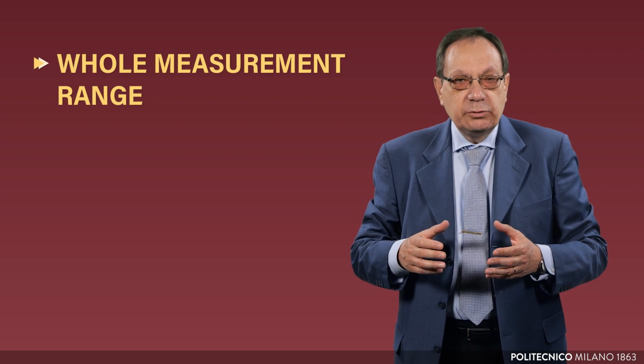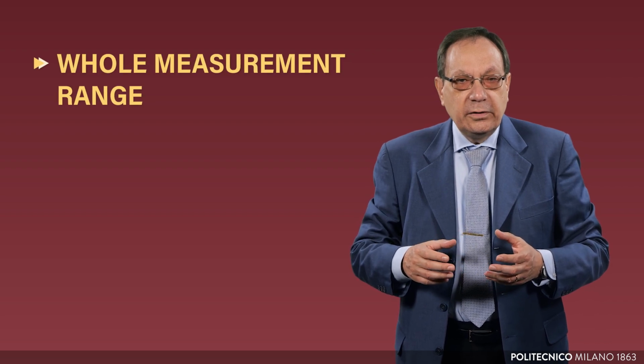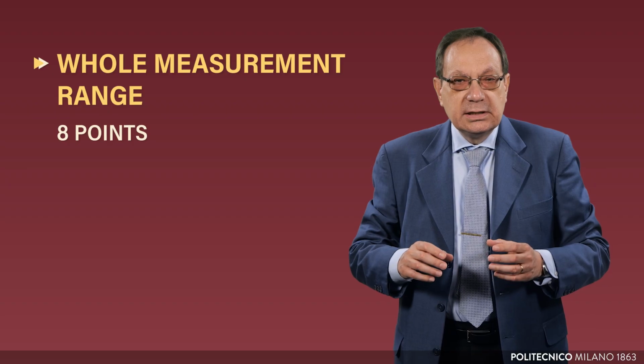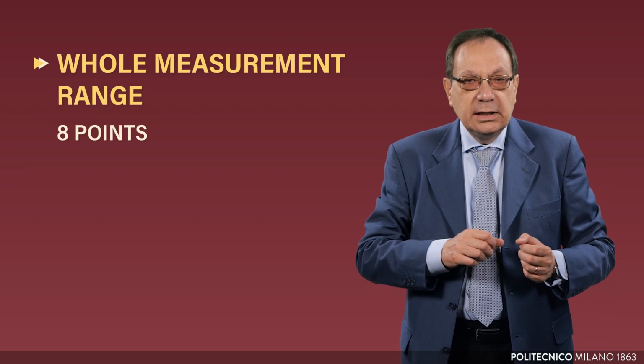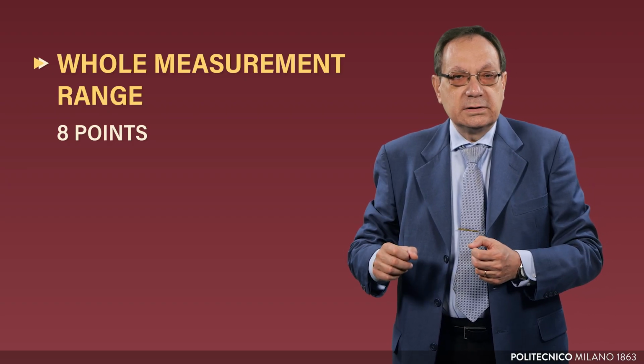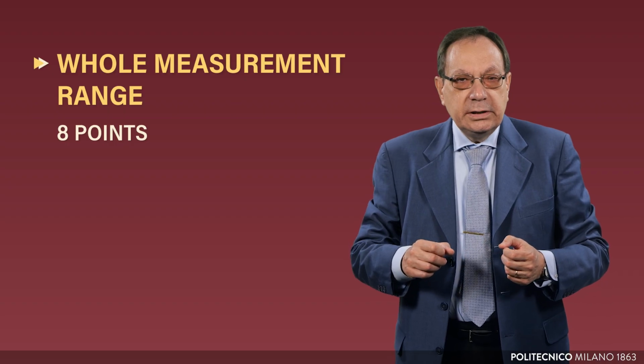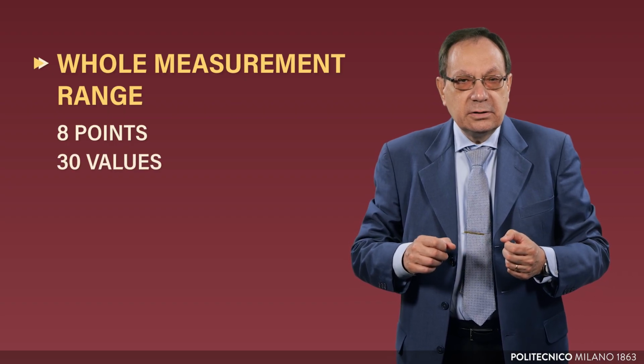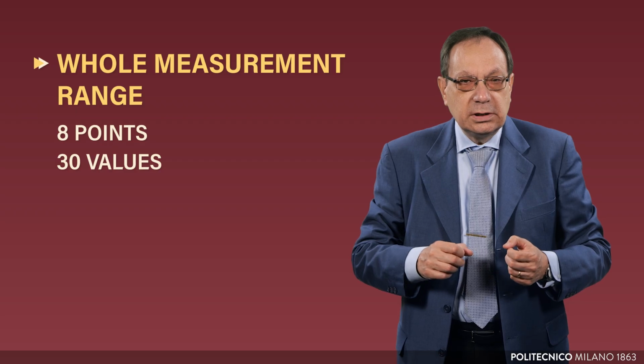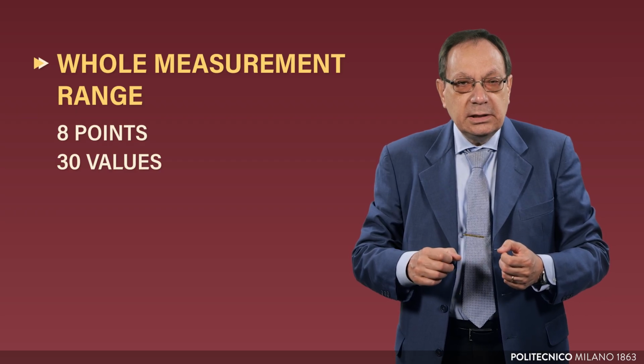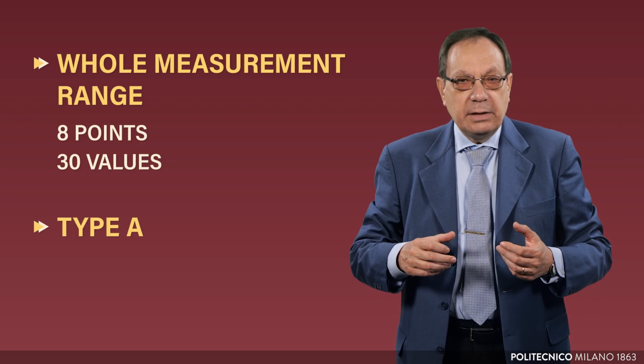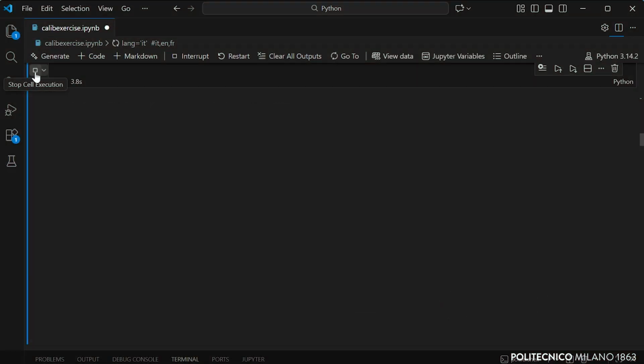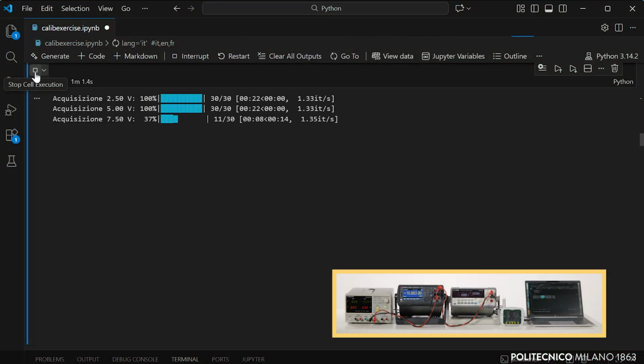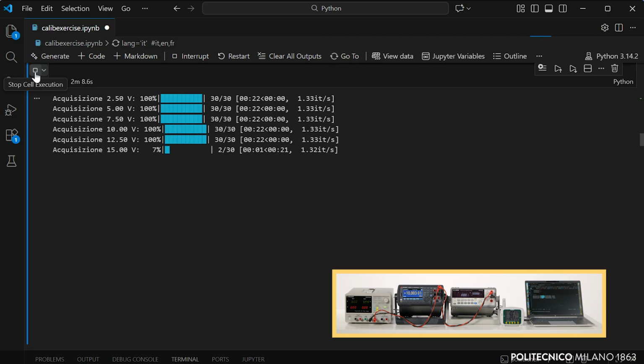As we saw in the previous video, we need to take into account the entire measurement range that we are calibrating. We have therefore set 8 measurement points starting from 2.5 volts, evenly spaced by 2.5 volts. For each measured point, we record 30 values so that we can assess the uncertainty contribution given by the repeatability of the 2 instruments using a type A method. Let's start the program and let it acquire all the values that have been set.